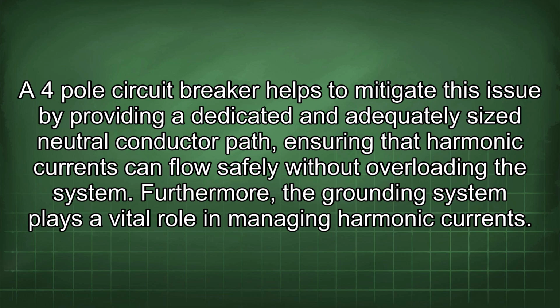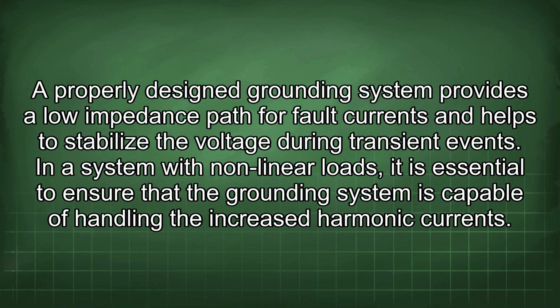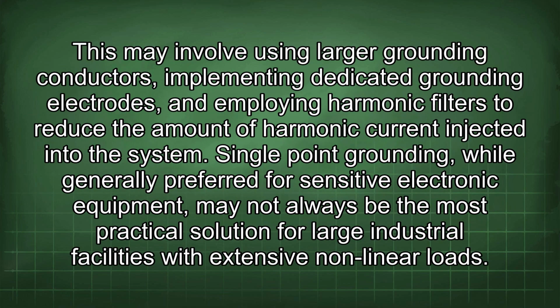Furthermore, the grounding system plays a vital role in managing harmonic currents. A properly designed grounding system provides a low impedance path for fault currents and helps to stabilize the voltage during transient events. In a system with nonlinear loads, it is essential to ensure that the grounding system is capable of handling the increased harmonic currents. This may involve using larger grounding conductors, implementing dedicated grounding electrodes, and employing harmonic filters to reduce the amount of harmonic current injected into the system.